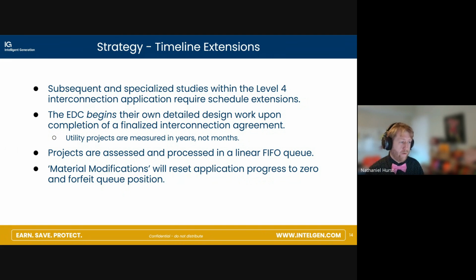Subsequent specialized studies with the level 4 interconnection require schedule extensions. So when stuff gets really weird, ComEd has a whole other list of studies that they may need to perform. These are pretty typical when it comes to level 4. And if you've ever had a project that was stuck at ComEd for longer than 6 months, they're probably looking at the substation or some other customer on your site, or some other weird, unique condition that requires actual engineers on their side to work on.